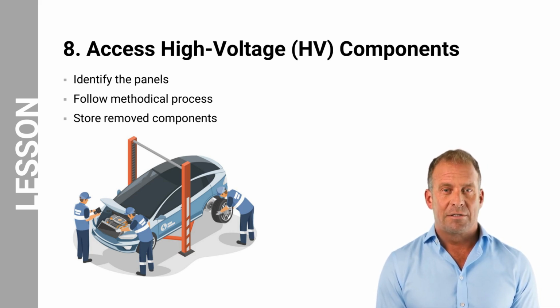Consult the manufacturer's documentation, including service manuals and safety guidelines, to understand the procedures and precautions for accessing high-voltage components. Identify the panels or covers that need removal. Before removing any panels or covers, confirm that the high-voltage system is de-energized using a Cat3 digital multimeter.